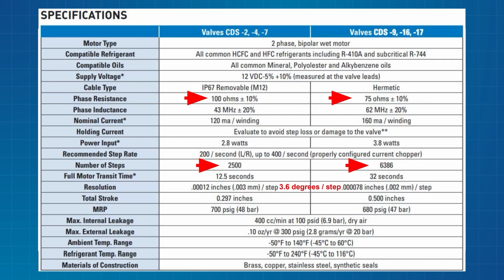The key components that I need to remember when I'm troubleshooting this - we talked about this with our EEVs. I can ohm across the motor windings, tell me if I'm open, I'm short, or if I have the right resistance or the wrong resistance. All of my small valves are 100 ohm. All of my large valves are 75. If I keep that designation, there's one piece I don't have to hang on to anymore.